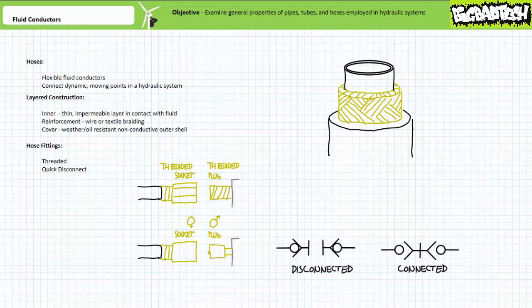Quick disconnects, in contrast, make use of a female socket and a male plug, both with interior check valves that are unseated when the plug is completely seated in the socket. When disconnected, the check valves close, and neither the socket nor plug leak.